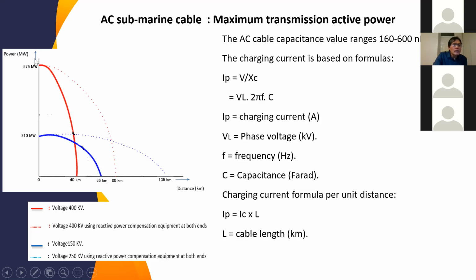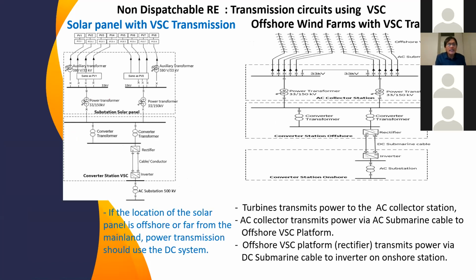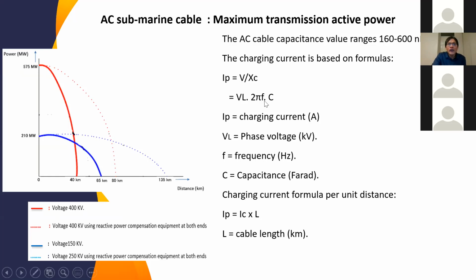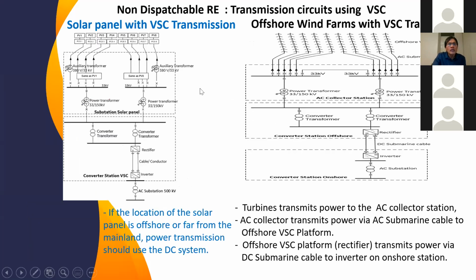Typically, for power of 575 megawatt with the voltage 400 kV, we can only transfer 40 kilometer. And then when we install reactive power compensation on both sides, offshore and onshore, we can extend the distance theoretically to 80 kilometer, but normally it will not be stable. This is the limitation for AC because of charging current. While for DC, we don't have frequency here. The frequency is 0. So we are not limited by the distance. Theoretically, we can deliver the power over long distance.